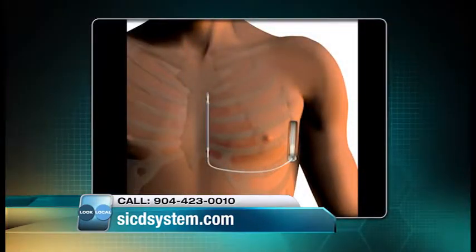The second is that these wires are sitting in blood vessels. Blood vessels have only a certain size, and if you have too many wires, it can clog up the vessel and you could have clots. And the third is that this wire is sitting inside of a beating heart. It's constantly being flexed, so sometimes you get failure of the wire because it breaks. So our systems that we've had for many years have had these problems where the wires could become an issue for the patient. More recently, a company, Boston Scientific, has released a device, and we'll see it pictured here in a moment, that sits entirely outside of the heart.